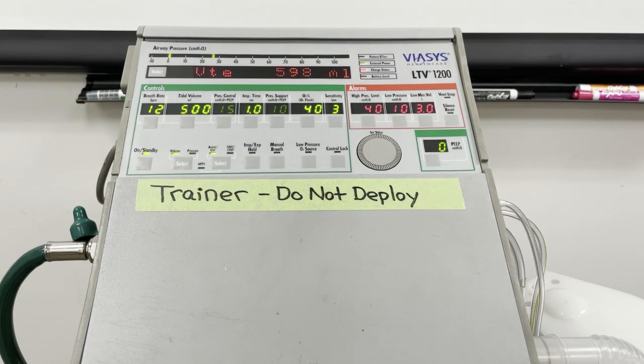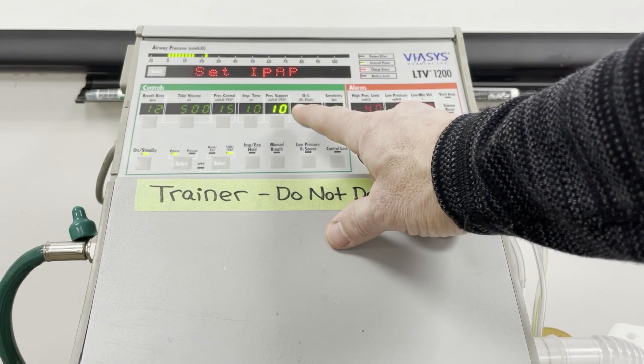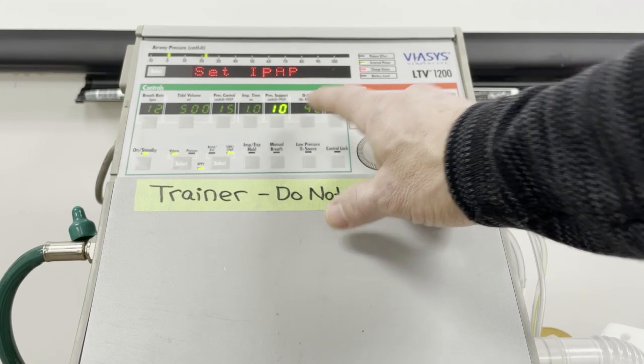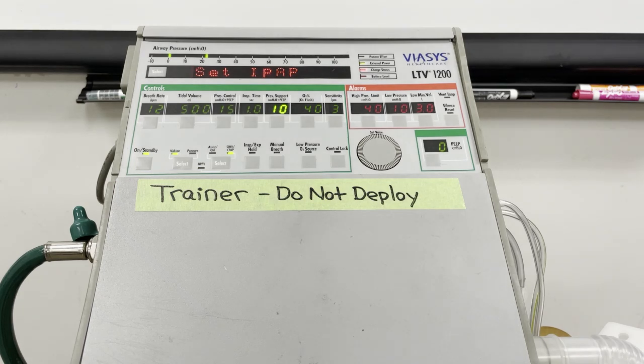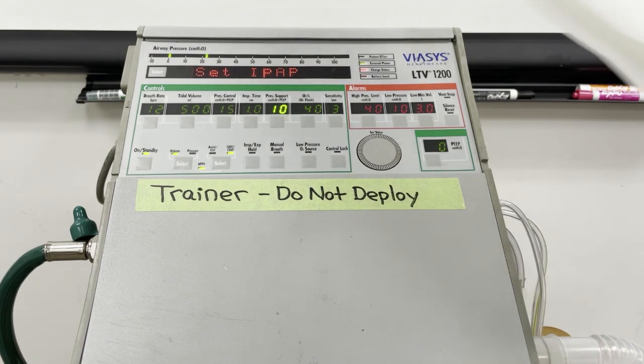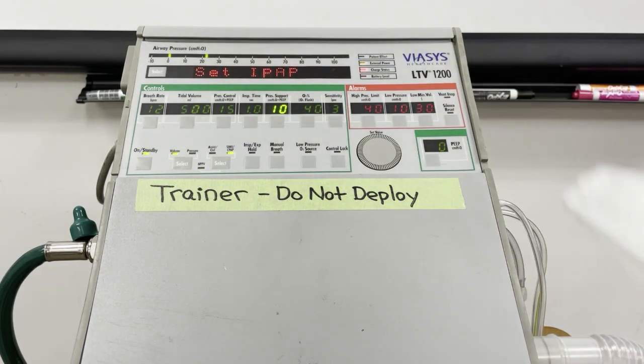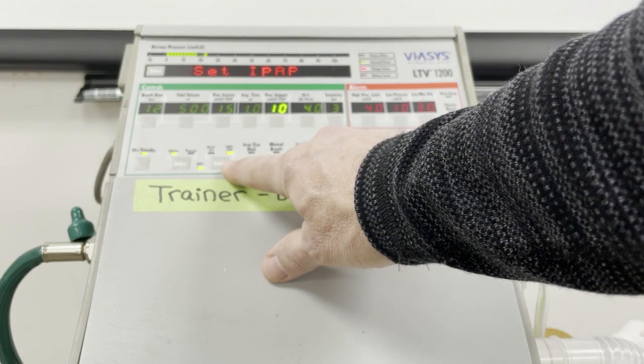When you set the vent up for BiPAP, the vent must be in operation mode. Prompts appear on the display screen when you reach NPPV mode, but they will be obscured if the ventilator has detected a problem. Having the lung simulator on allows me to show you the prompts. I made a second video without the lung simulator so you can see the difference. As I was saying, once the vent is in normal operation, you can toggle the mode button to get to NPPV. When you reach NPPV, the display screen will prompt you to set IPAP.